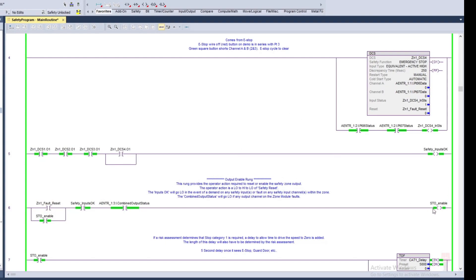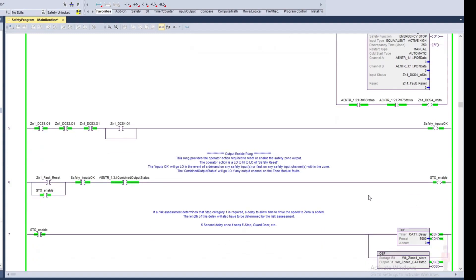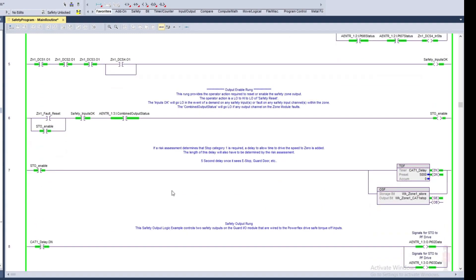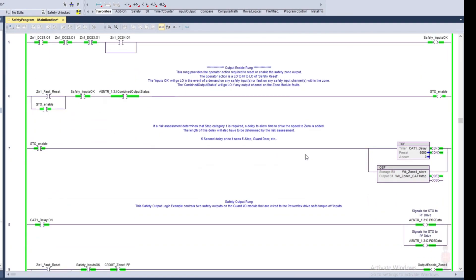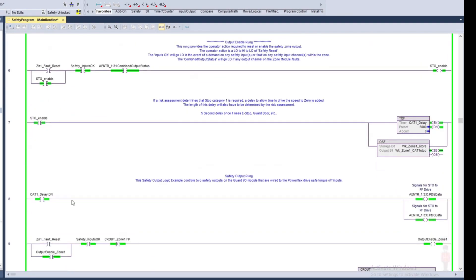And in this case I'm just calling this my safe torque off enable, and once the safe torque off enable says I'm okay to go, I'm going to turn on the outputs on my safety card to go to the safe torque off terminals on my VFD.